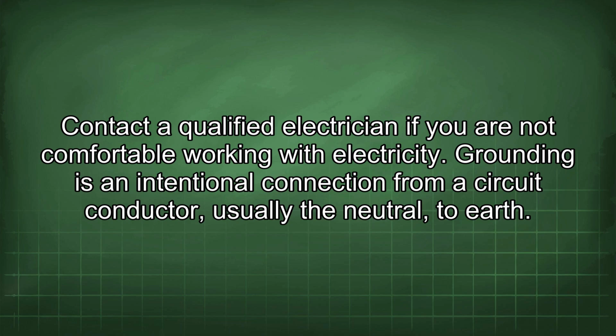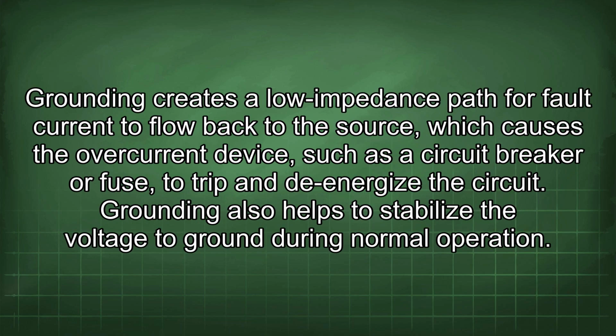Grounding is an intentional connection from a circuit conductor, usually the neutral, to earth. Grounding creates a low impedance path for fault current to flow back to the source, which causes the overcurrent device, such as the circuit breaker or fuse, to trip and de-energize the circuit. Grounding also helps to stabilize the voltage to ground during normal operation.